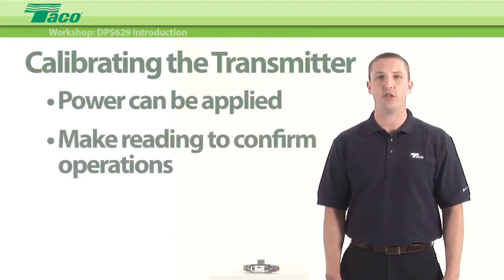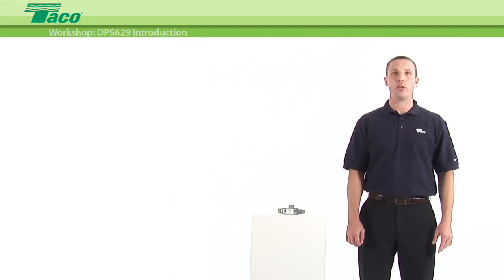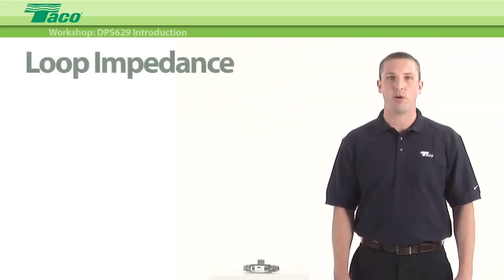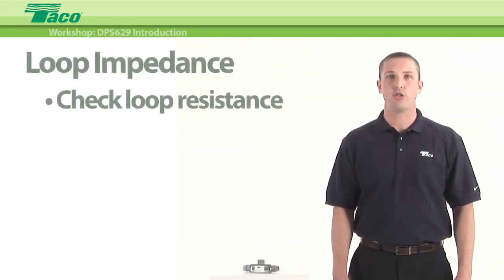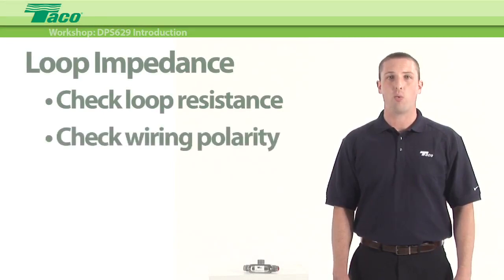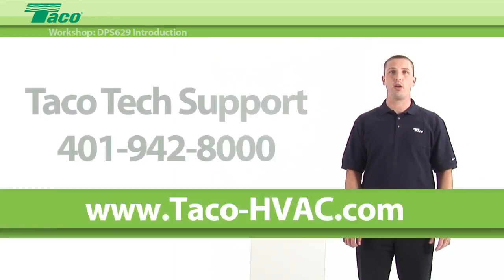The DPS629 should not exhibit any field performance issues, and most issues are related to wiring the unit and should be exhibited during startup. If the readings appear to be inaccurate, you may wish to check the loop resistance and that the wiring polarity is correct. If any other issues are observed, it is recommended to contact the TACO technical support team.